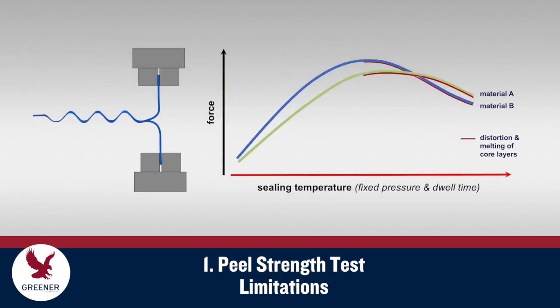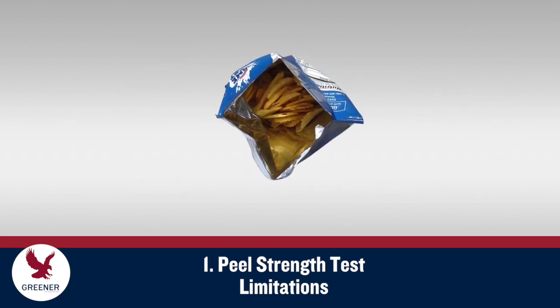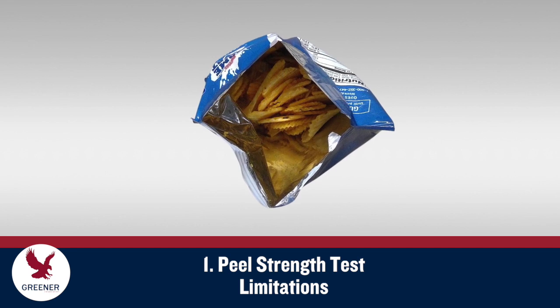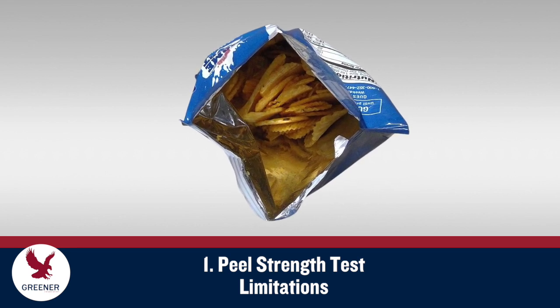Set points for temperature, pressure, and dwell time are typically standardized to ensure repeatability and inter-lab correlatability. They don't necessarily represent production settings, and therefore don't indicate real-world results. Sometimes seals are tested by pulling them apart by hand. This method does not produce repeatable peel-strength results, though a seal that fully delaminates across the package width indicates seal strength that exceeds the material's tear resistance.